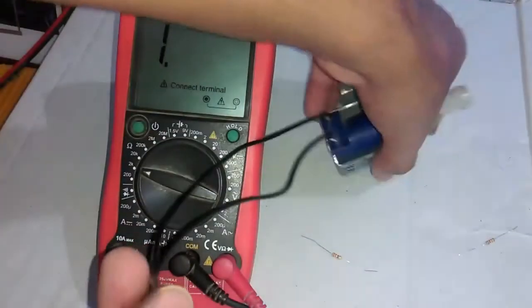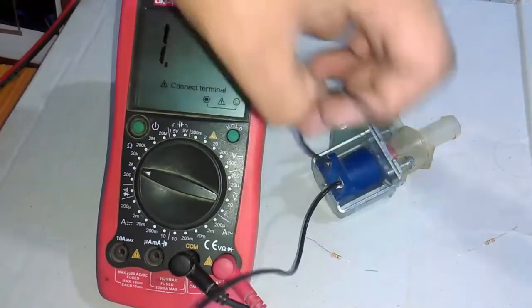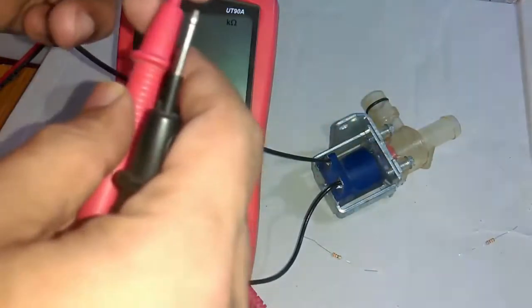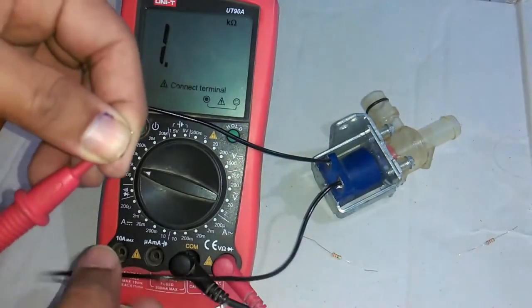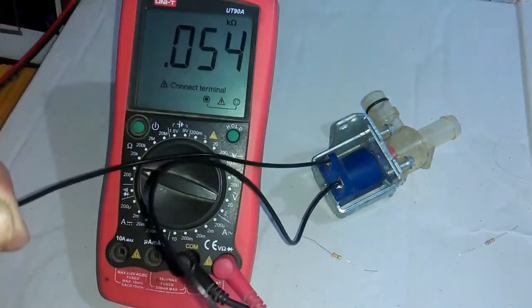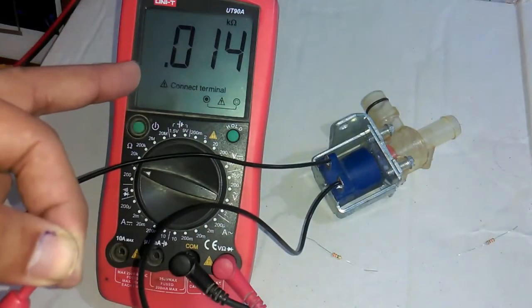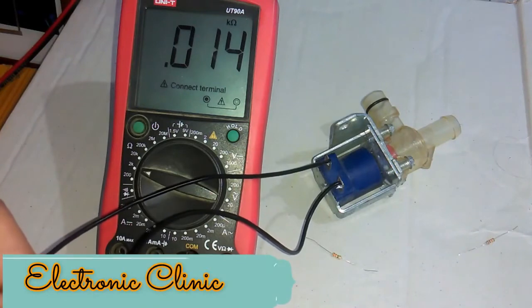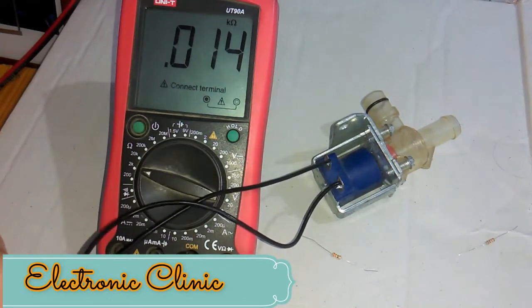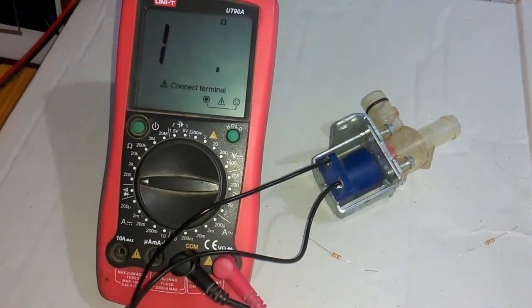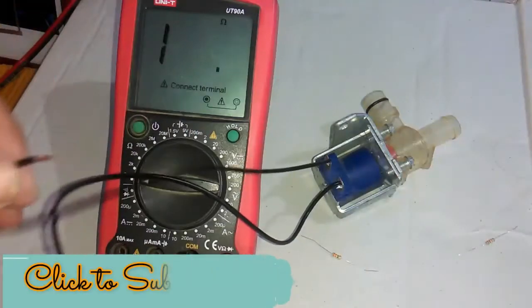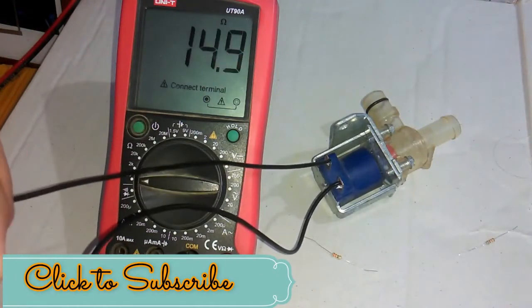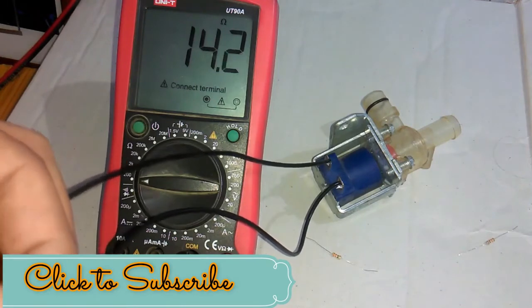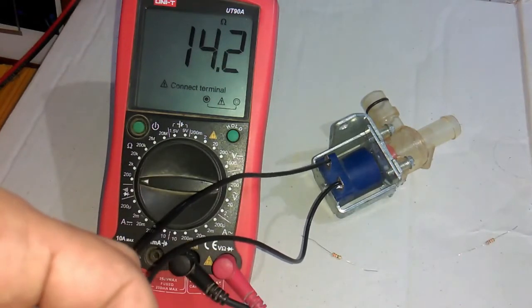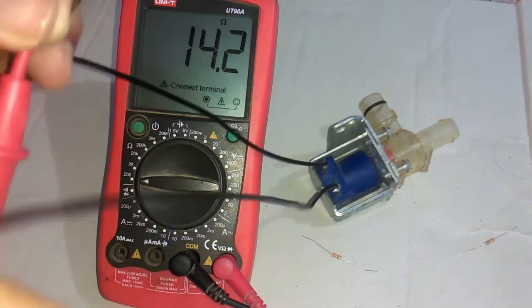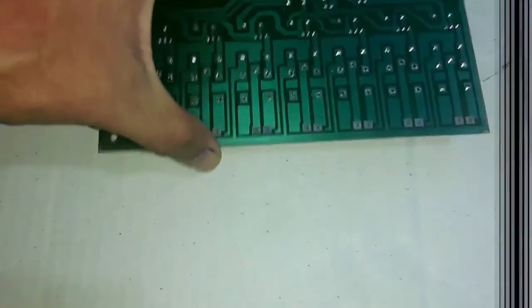Now let's find the coil resistance of the solenoid valve. It has two wires, so connect one with the red test lead and the other one with the black test lead, and in the same way it doesn't matter which test lead you connect with which wire. As you can see it's 0.014k, so let's reduce the value and check again, and now you can see its resistance is 14.2. So using a digital multimeter we can also find the resistance of the coil.